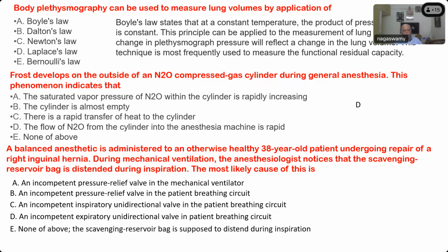The scavenging reservoir bag is supposed to distend. Option D, sir. An incompetent expiratory valve. Incompetent pressure relief valve in the mechanical ventilator. Actually, the bag is supposed to collapse during inspiration and expand during expiration. Then only it indicates that the gases are going out, isn't it? So an incompetent pressure relief valve in the mechanical ventilator will allow the gas to de-inflate.